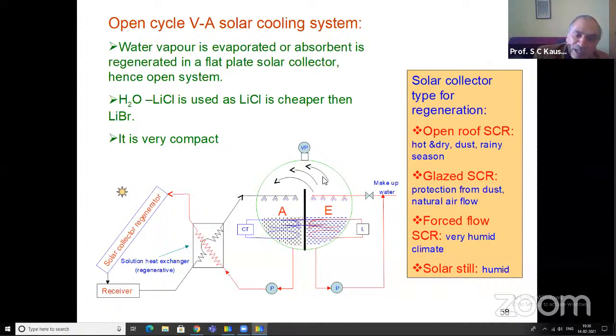Now the water vapors which are generated go to the absorber chamber, where a solution of the refrigerant, say water lithium bromide or water lithium chloride or water calcium chloride, is being sprayed. That solution has a tendency to absorb this water vapor. It will become dilute in the absorbent and rich in water. It is collected here, and because of the absorption process, heat would be rejected, which is removed by the cooling tower, a simple cooling tower, or just by circulating water for cooling this solution.